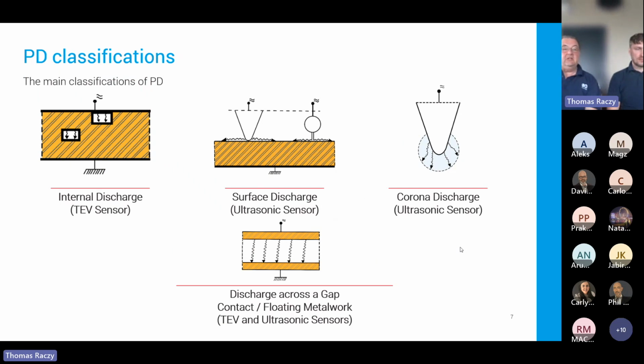Different partial discharge classifications. We've got the internal discharge, which obviously we're using the TEV sensor on the handheld unit to detect. We've got the surface discharge, where we use the external accessories, including the onboard built-in microphone on the handheld unit. Corona discharge, which again will be using headphones and external sensors, and we've got a discharge over the gap, floating metalwork, which you can use both sensors.